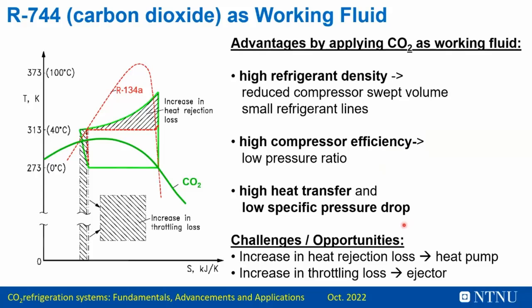Of course, there are challenges, and one challenge you can see on this, the increase in heat rejection loss compared to a traditional condensing cycle. However, we can use this increase in heat rejection loss in the heat pump to produce high temperature water. A high temperature lift on the gas cooler is possible, and that's why it is so beneficial to utilize heat recovery whenever it is possible with the CO2 system. The next challenge or opportunity for CO2 is the increase in throttling loss at elevated temperatures. So this area becomes bigger and bigger the higher the temperature. This expansion work can be utilized because it is much higher compared to traditional fluids. So that's why we can, for example, utilize an ejector.